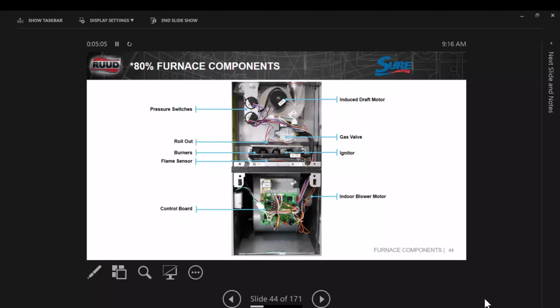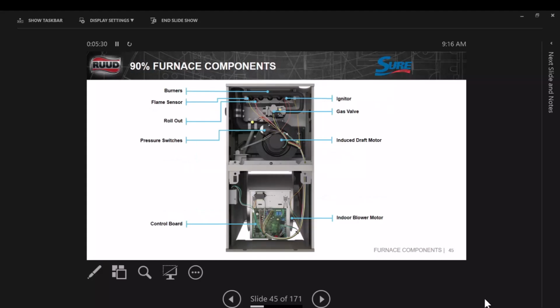Same thing with the pressure switches. The low and high pressure switch is wired separately, so you'll be able to tell which one is tripped or which one is giving you troubles. Your app will also tell you why the unit's running. This switch is closed, this switch is closed, and you can monitor all the switches in there through the app. Still spark ignition. 90% furnace is basically the same thing.